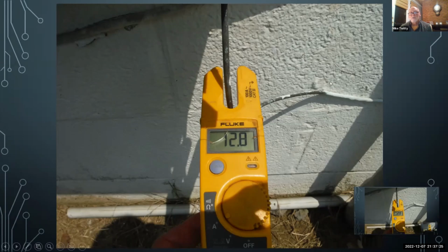Now, I've had home inspectors tell me that when they check a grounding electrode conductor, they'll give it a tug to make sure it's good and tight. Guys, don't do that. If you had pulled this one loose, that 12 amps is going through you to the ground, and you're going to die right there. Equipment grounding conductors can kill you if there's a fault on them, because they will carry current when there's a fault. So don't be pulling on those guys.